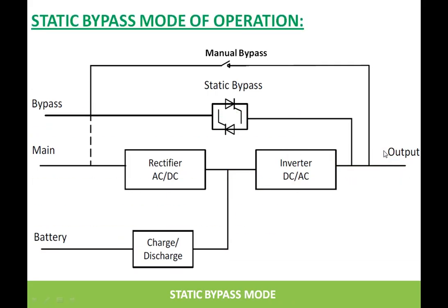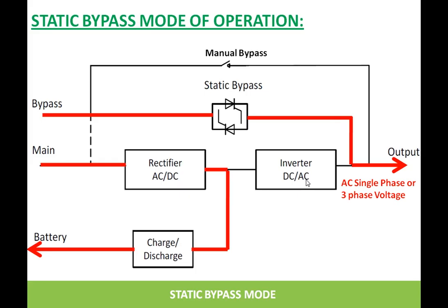The other mode is the static bypass mode. In this mode, the static bypass switch is used for providing the output. The UPS goes to this mode when the inverter fails or the inverter overloads. Inverter overload occurs when the load connected to the UPS draws more power than the capacity of the inverter. Under these conditions the UPS goes to this mode, and the power flows through the static bypass to the output. The battery bank is still in charging mode because the rectifier is in operation.